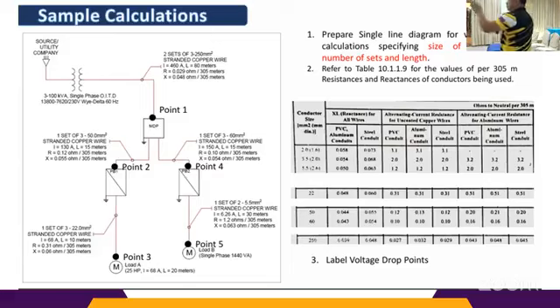Then for the others down there, we have 1 set of 3 22 mm square stranded copper wire. Then we have a given current of 68 amperes, length is 10 meters, going to the motor at 25 horsepower at point 3. Then another side, we have point 4. Yung wire po natin, 3 of 60 mm square, so that is 3 phase. Current is 150. Then, down to point 5, meron din tayong load na single phase, 1,440 volt ampere, 5.5 mm square po yung wire po niya. Then, we need to compute. You prepare a single line diagram and the voltage drop calculation, specifying the conductor's number of sets and length. So, refer to table 10.1.1.9.